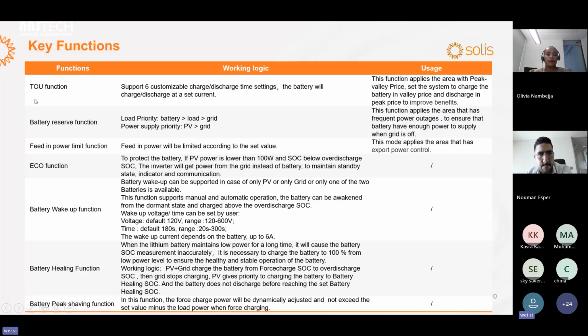Okay, for the key functions, we have the TOU function, so you can set 6 charging and discharging time settings, and we have the battery reserve function, so you can keep the battery SOC at a certain value you set. About the feed-in power limit function, you can set zero power to feed in to the grid. The eco function, wake up function, healing function and peak shaving function are designed to help the battery work.